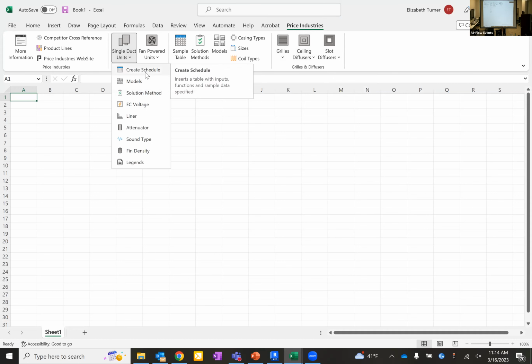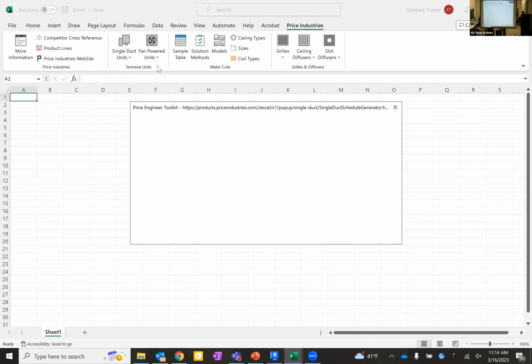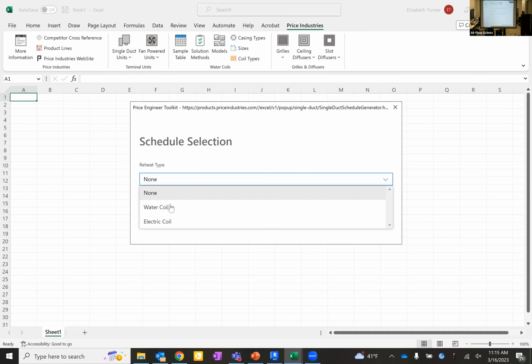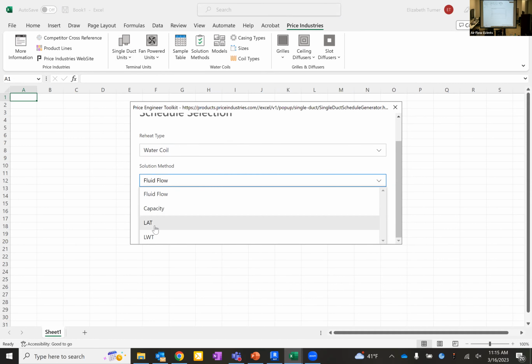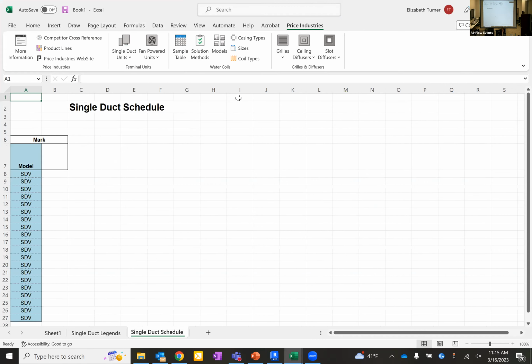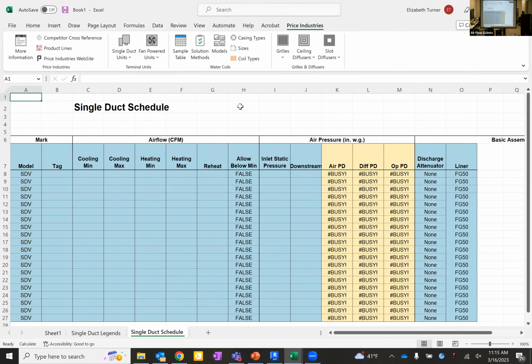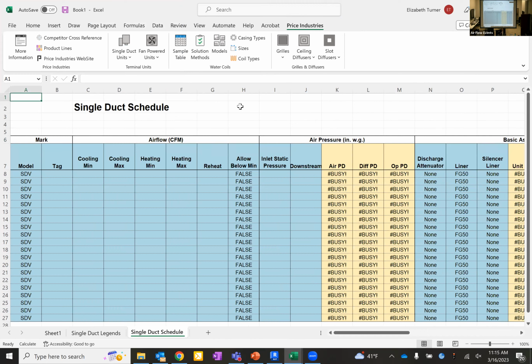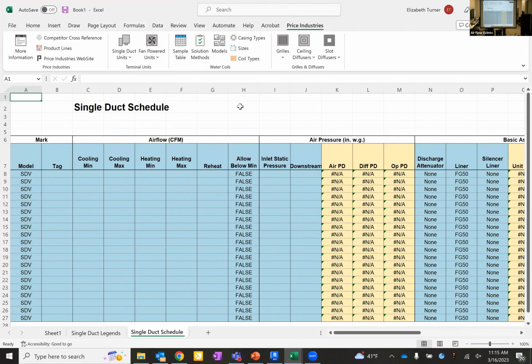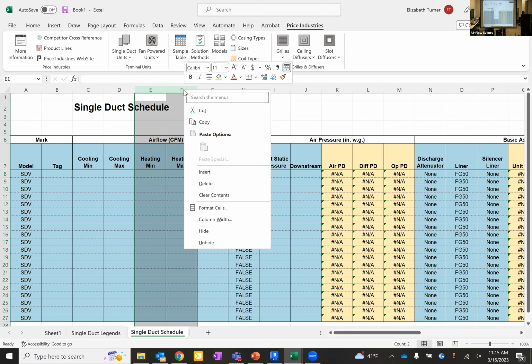So I'll run it through an example real quick of a single duct schedule. Maybe we'll throw a hot water coil on it and we'll solve for leaving air temperature. Go ahead and click generate schedule. Now this first feature here will give you a massive pre-built schedule with every performance parameter you could possibly need. Engineers are probably not putting this much detail on their specs. So again, it is still just Excel. I could go in and remove columns, move columns, customize it to make it what I want.